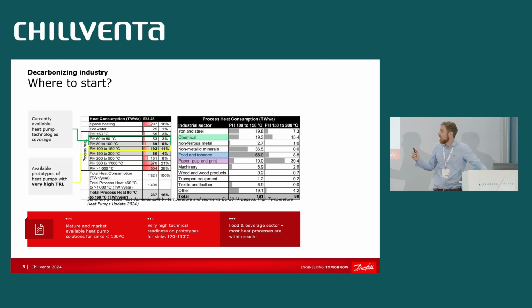The next step is going above 100 centigrade. Why? Because you need to generate steam, often low pressure steam, in among others food and beverage applications. The next step, which is, I believe, very close in terms of development of technologies, is 130 degrees condensing. With 130 degrees, as a first step, you can generate low pressure steam, 2-bar, which is often sufficient in multiple food and beverage processes. If higher is needed, then you can recompress it with MVR, vapor recompression cycle.